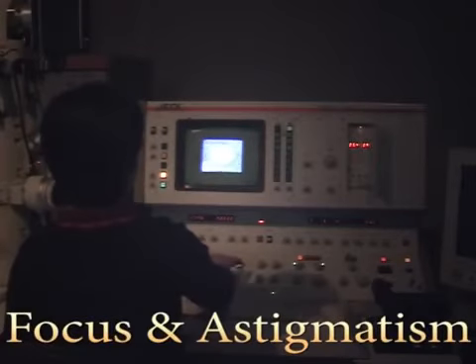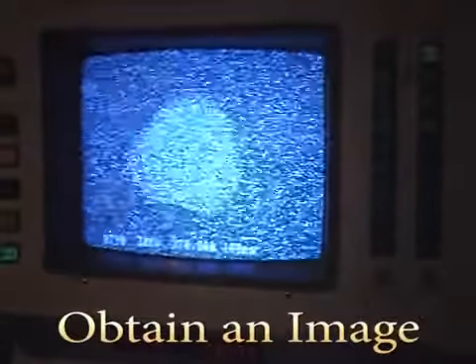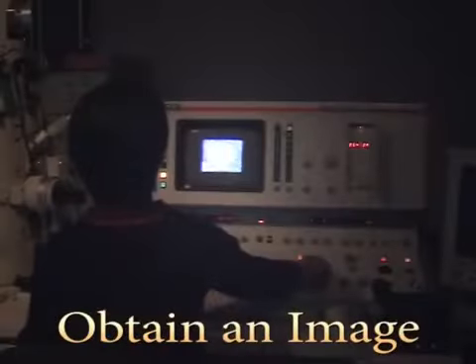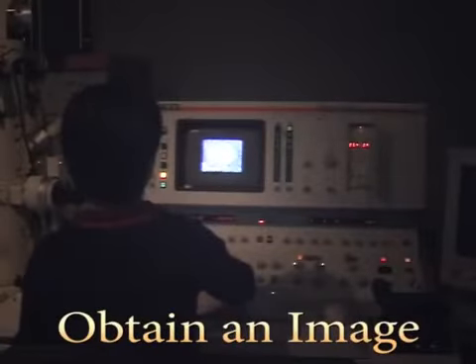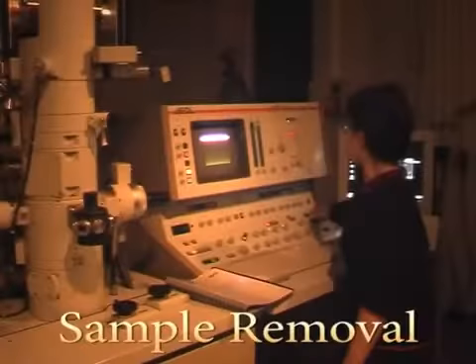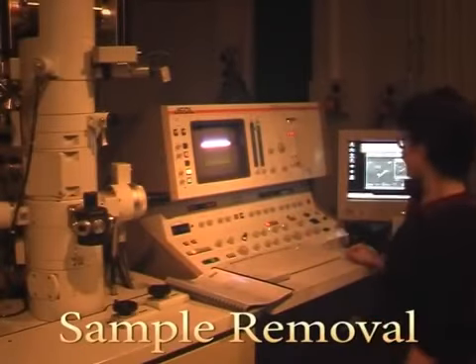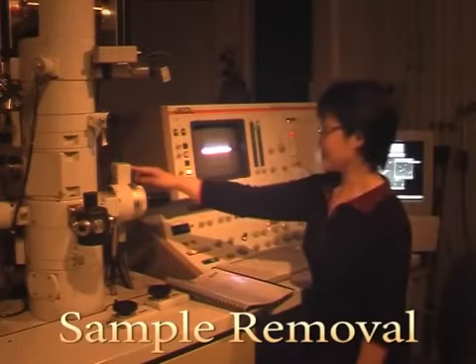Focus the image as best you can. Adjust the XY stigmators for the best image. Press the accelerating voltage button off. Make sure that the valve V7 is closed.